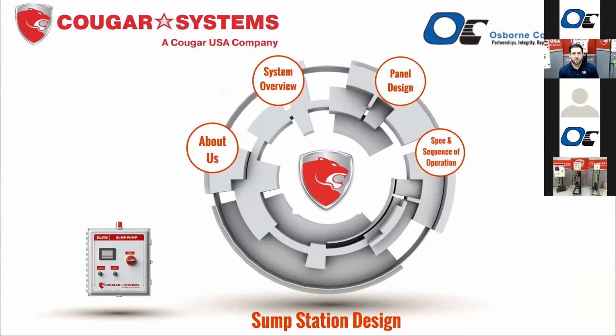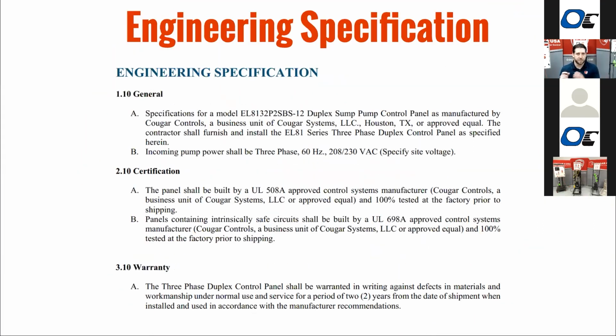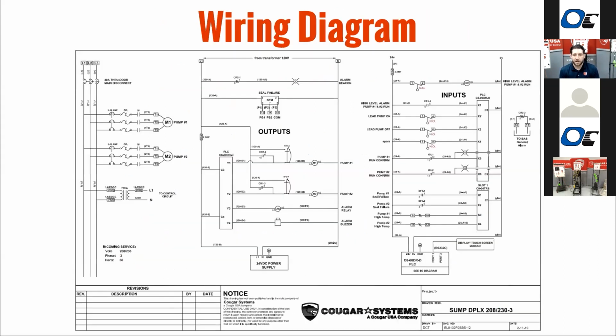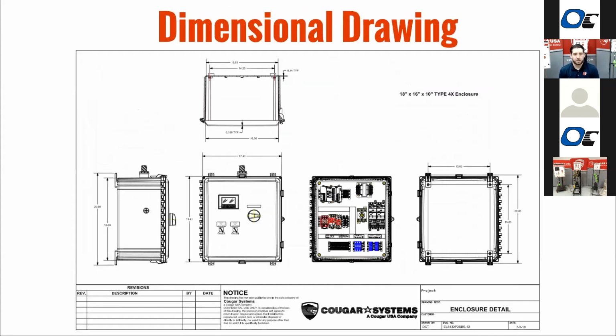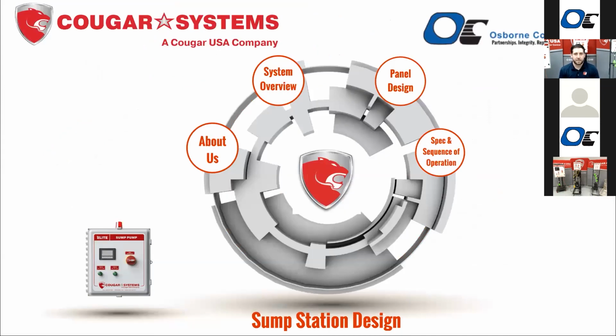Okay. So that covers some of the system design, the applications, a little bit on some of the internals, the components there, and I just want to show you what would go along with this from a design perspective. Something we could support Osborne and y'all with in terms of the design would be the engineering specifications. So we have the specifications pulled together for these different applications, as well as sequence of operation, the wiring diagrams, and the drawing that I showed you earlier of the entire sump basin. It includes where to put the pumps in the bottom, where to penetrate on the cover. All of those things are part of that drawing, as well as an enclosure drawing there, so they can know where to mount and things like that. So all of that would be provided as a drawing package or design package for y'all on the design side.